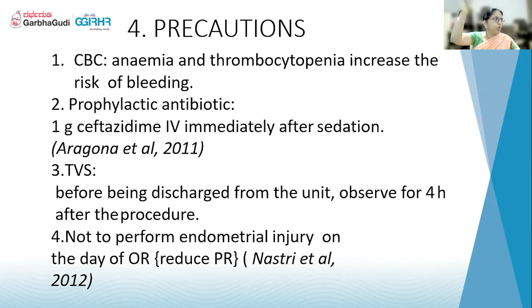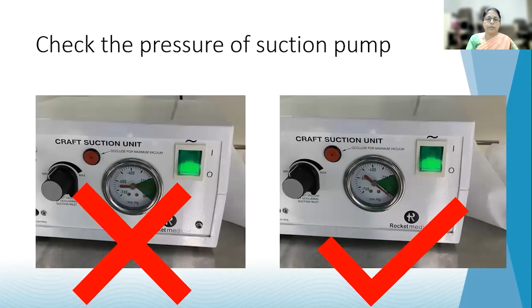As I told you, check for the cap fitting over the tube. This is the most common mistake for follicular fluid not coming - a very simple mistake, but we are not cautious sometimes. You have to snugly fit the cap for the pressure to suck the fluid. Also keep the pressures properly monitored during the procedure - keep it between 90 and 110, not more than 120, because it will damage our oocytes completely.